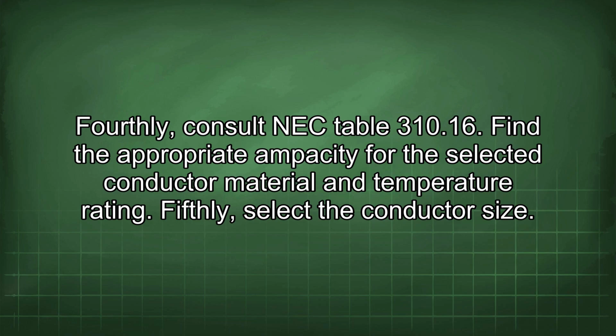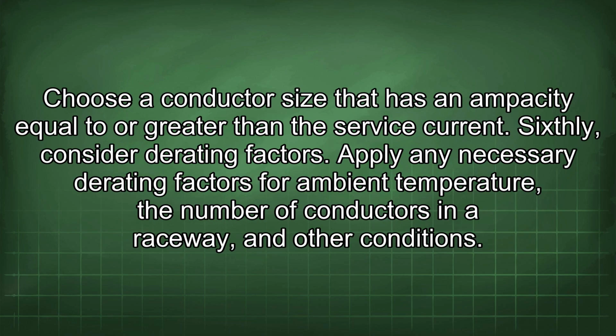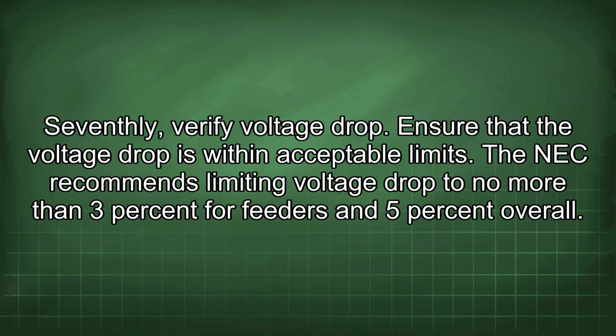Fifthly, select the conductor size. Choose a conductor size that has an ampacity equal to or greater than the service current. Sixthly, consider derating factors. Apply any necessary derating factors for ambient temperature, the number of conductors in a raceway, and other conditions. Seventhly, verify voltage drop. Ensure that the voltage drop is within acceptable limits. The NEC recommends limiting voltage drop to no more than 3% for feeders and 5% overall.